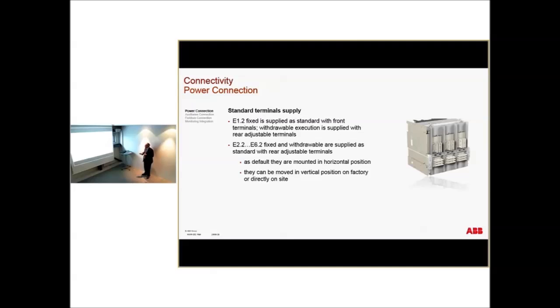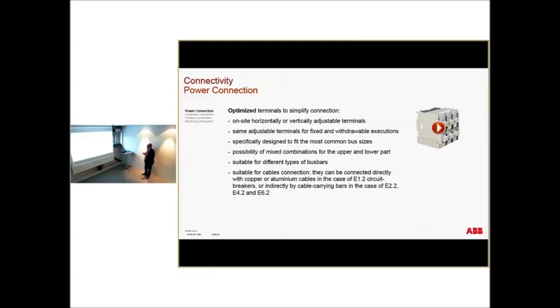In this case, you have the possibility to turn the rear terminals. They are square, and you can buy the rear horizontal and decide by yourself to put it in the vertical position. Or through a dummy code, you can ask the factory for the rear vertical one. Mixed solutions are possible: vertical on the top, horizontal on the bottom, or different sorts of breakers. So basically, this can accommodate the different panel builder systems. And this solution is available on all the range as a standard. As far as the smaller breaker is concerned, copper and aluminum cables are also available as a standard.